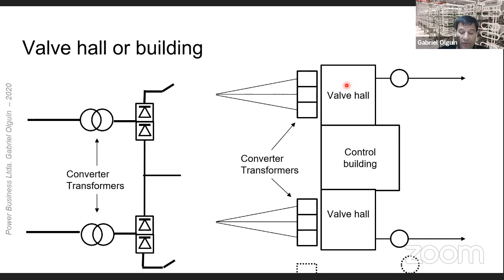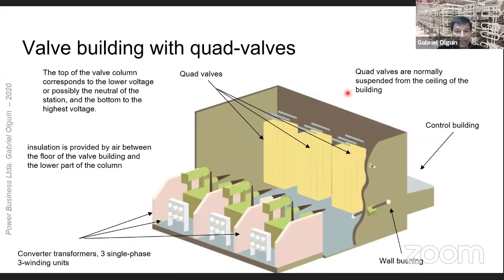The converter transformer configuration determines the configuration of the valve hall, as we will see in the coming slides. This slide shows a valve hall isometric with the valve legs hanging or suspended from the ceiling of the building. The most common valve arrangements are quad valves and V valves. In the quad valve arrangement, the 4 valves corresponding to each of the 3 legs of the 12-pulse valve group form a column that hangs or is suspended from the ceiling of the building.